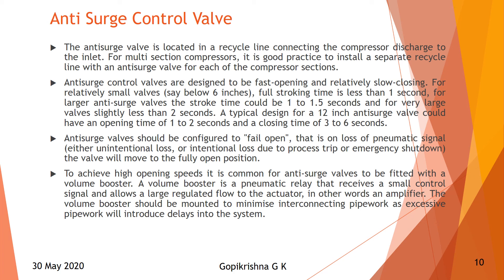Due to loss of pneumatic signal — either unintentional or intentional due to process trips or emergency shutdown system — the valve will move to the fully open position. To achieve high opening speeds, it is common for anti-surge valves to be fitted with volume boosters. A volume booster is a pneumatic relay that takes a small control signal and allows a large flow to the actuator — in other words, a simple amplifier. The volume booster should be mounted to minimize interconnecting pipe length, as excessive piping would introduce delay into the system.